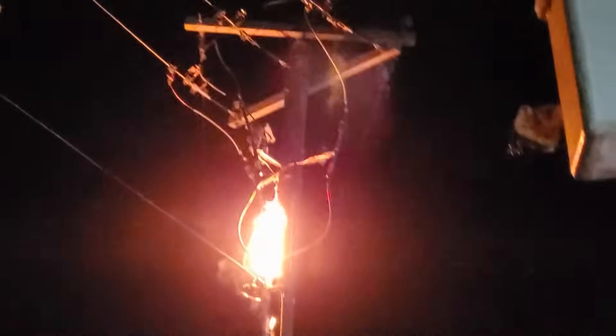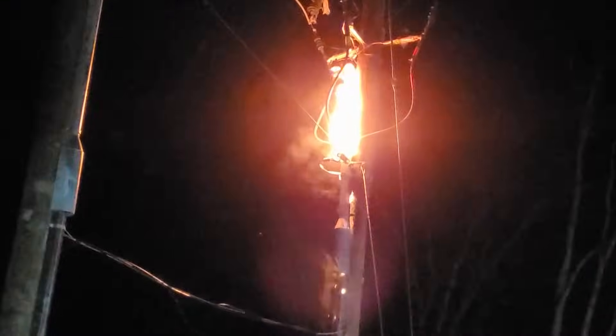The contractor quickly went to the job site, saw that the pole was on fire, called me back up on the phone, at which point we notified our dispatcher. We got some grounds back on the line and they put the fire out. As you can see in the footage, it was a pretty dramatic fire. There was one splice that failed and the cable caught fire, which completely destroyed the rest of the cables and a little bit of the pole.